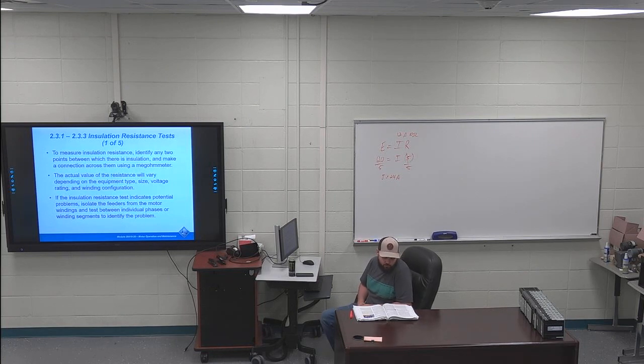I do have the first sentence of the shorts bullet point in the bottom right of page 22 highlighted. A short occurs when 2 or more windings of separate phases contact each other at a point, creating a path other than the one intended. So like I said, windings have that clear insulation. If that insulation wears down, they can be connected, and it's a phase-to-phase short.